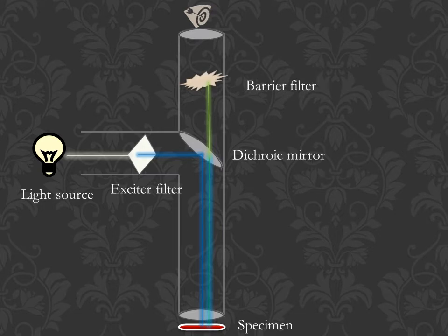The filter name is barrier filter. As the name suggests, it is going to filter some residual blue light. If it is still there, then it filters the remaining blue light, so that when the final ray is obtained, it would be of entirely green color. This green color light is visible.